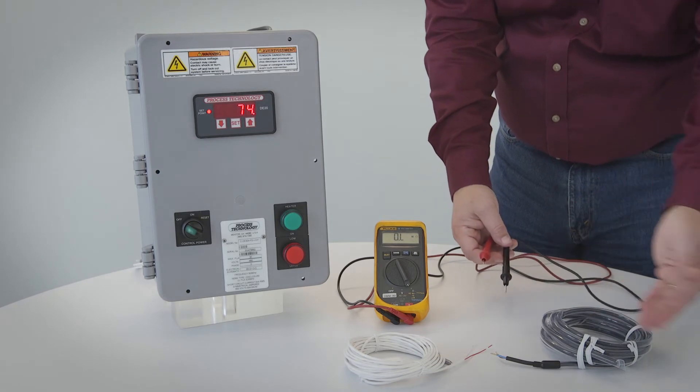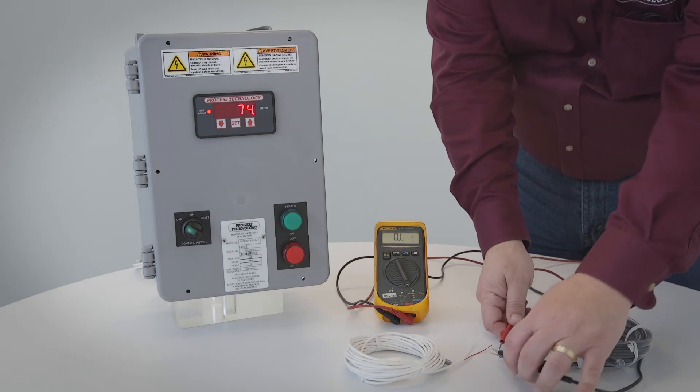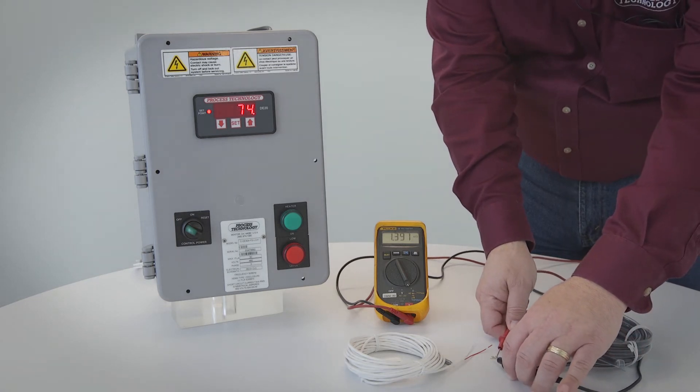The DLC series controllers use a thermistor sensor. This sensor should read around 990 ohms at room temperature.